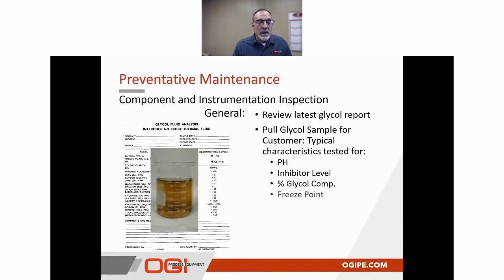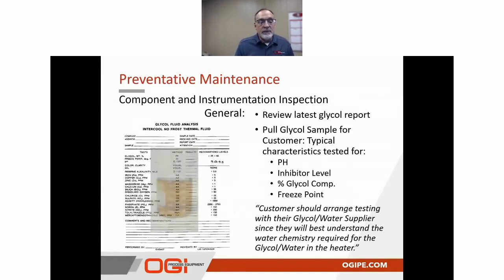In this case, after we've reviewed that, we want to go ahead and pull a sample and have it analyzed for the typical characteristics that glycol should be performing to. And that can be conducted, as noted here, by the customer's glycol water supplier. Typically, whoever supplied that water glycol has the best understanding of the glycol water composition and characteristics that ensure that chemical makeup is correct for the particular inhibitors that are in that glycol media. And also it's a good indication of them looking for trace metals on a historical basis. You can kind of judge where your glycol concentrations and its performance are running, as long as you're finding minimal trace metals in any sample that you're taking.